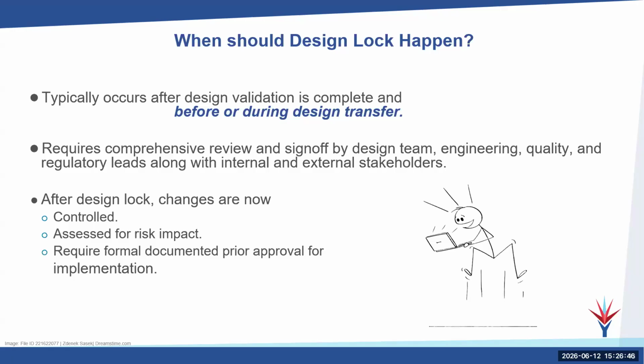After design lock, this is where it gets really critical that changes remain controlled. If you lock a product and you decide you're ready to move forward, but then you decide to start making changes, that's okay, as long as they're controlled and assessed for the risk impact, and that you have the required formal documentation of the prior approval for implementation. So when you reach a point where it's locked, it is the product, but we're going to make a change. Now it becomes a defined and controlled process to move forward.